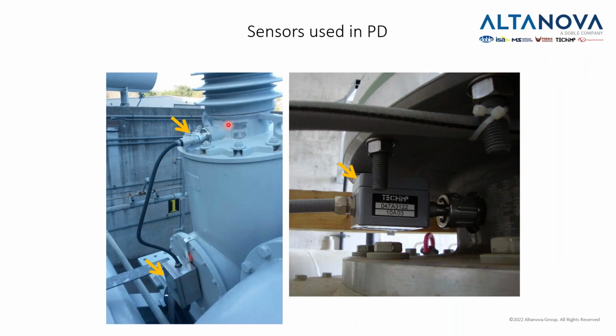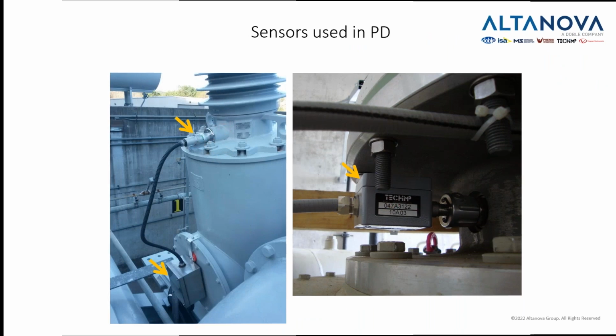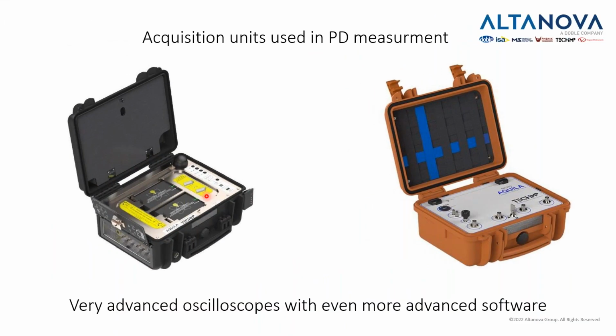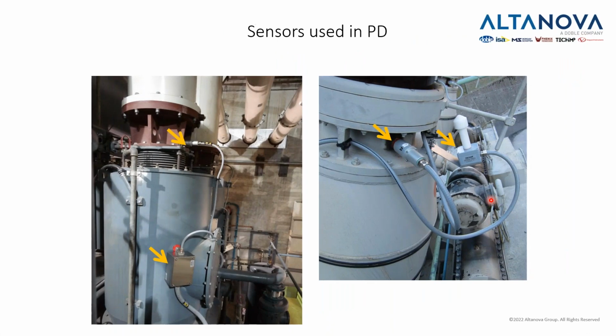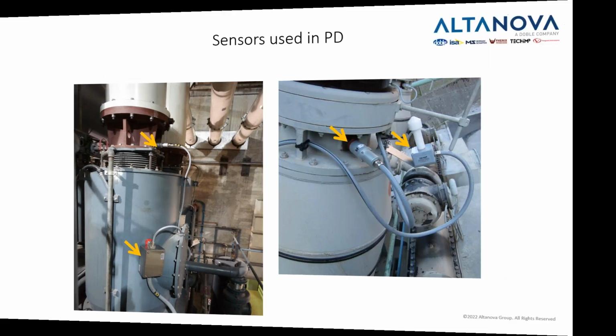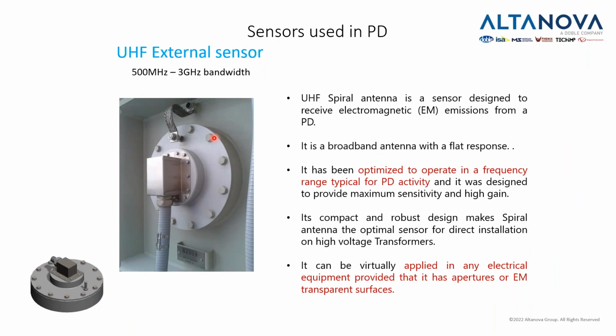So this is where the sensors lie, at the bottom of the bushing. This is where you would connect your acquisition unit, and let's not forget, this is an acquisition unit. This one is called Aquila, and this one is called Micro Aquila, and effectively these are very advanced oscilloscopes with even more advanced software. This would be that advanced software. Now, these are some more examples. Actually, this is an example of a monitoring system which can monitor partial discharge and tan delta at the same time. These are some additional sensors used not so often.